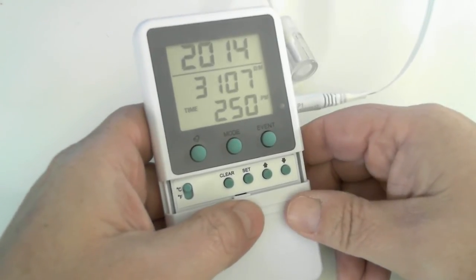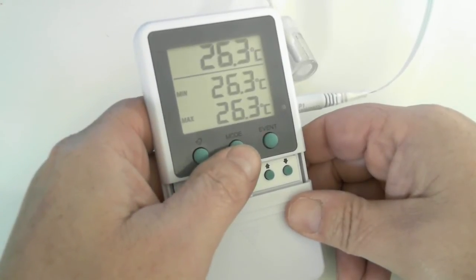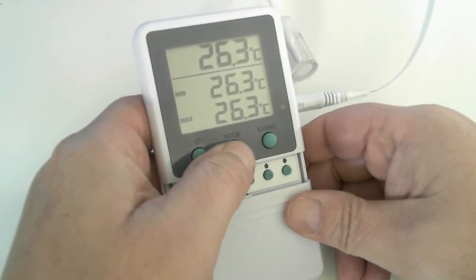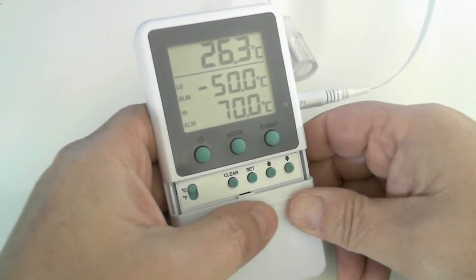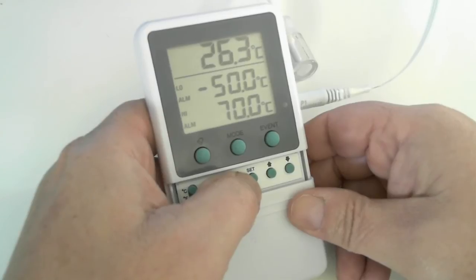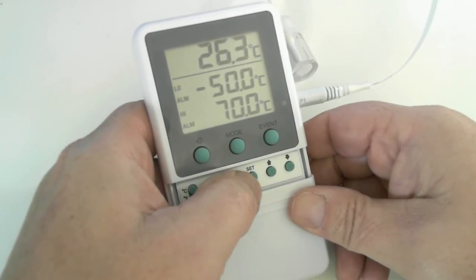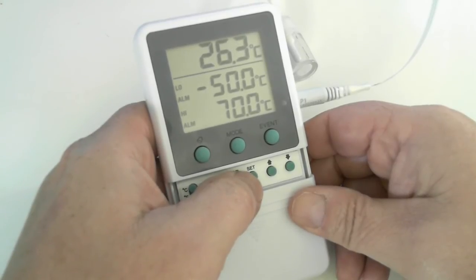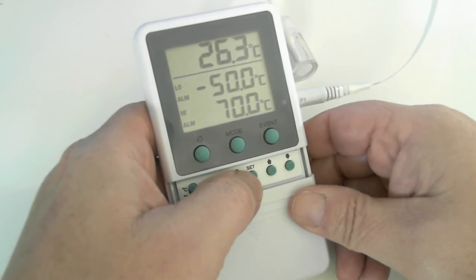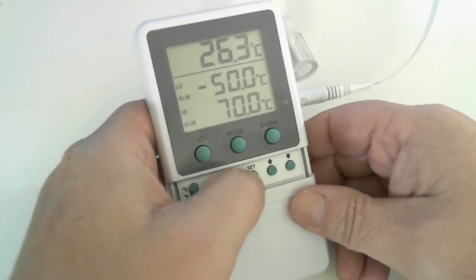Now let's go and configure our alarm settings. Hit the mode. There's our current min-max screen. Let's go one more time. And here's our alarm setting screen. It currently has a low alarm set point of minus 50 degrees C and a high of 70 degrees C. But we're going to be setting our unit up for common vaccines, and they generally are in the range of 2 degrees C for a low alarm setting and 8 degrees C for a high. So hit the set button.